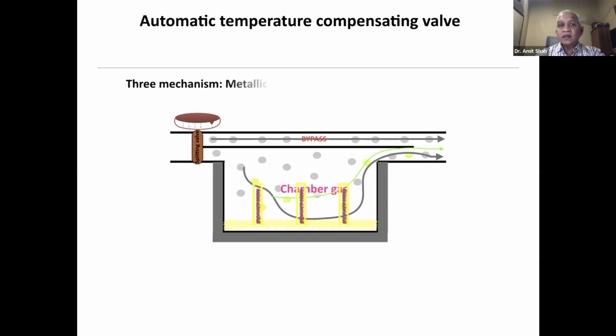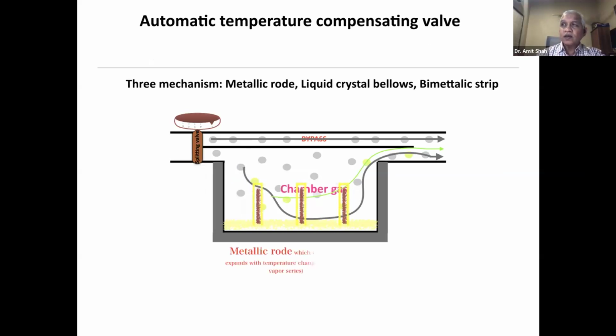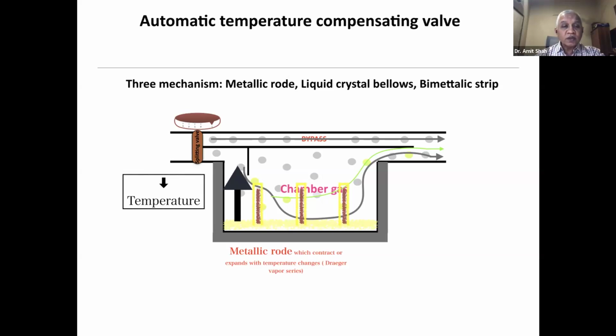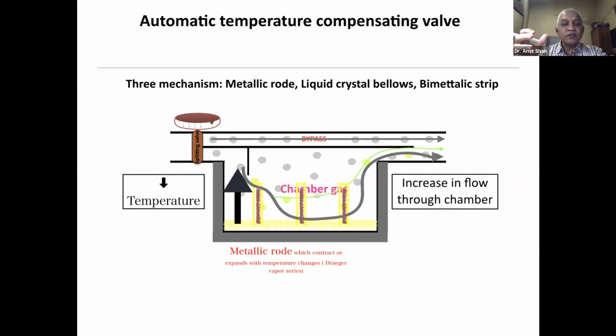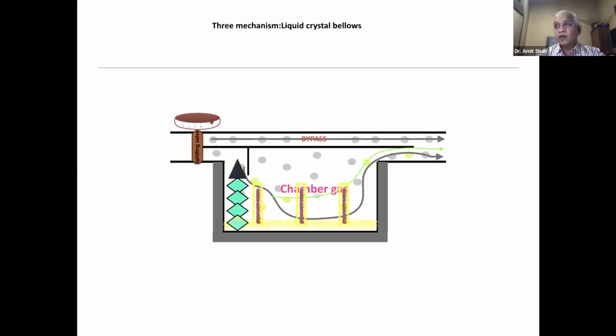Okay. And the temperature compensating valves are of three technologies. One is a metallic rod. Okay. Second is a liquid crystal bellow, and third is a bimetallic strip. So the metallic rod, which contracts or expands with the temperature, is part of the Draeger Vapor series. The metal can easily contract and expand with the temperature. So if the temperature drops, it constricts, we know it shrinks. It allows more flow to pass through the chamber. If the temperature increases, it expands and it will allow less flow to pass. Okay. The second is called liquid crystal bellows. The liquid is mainly ether, okay, or freon.